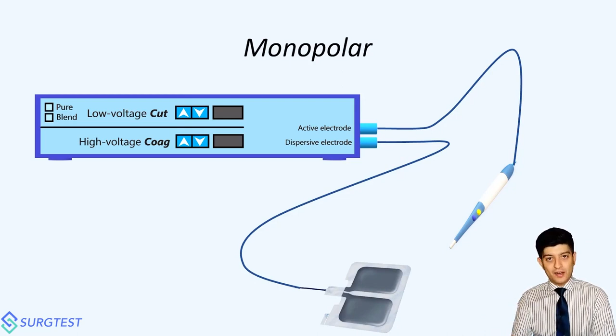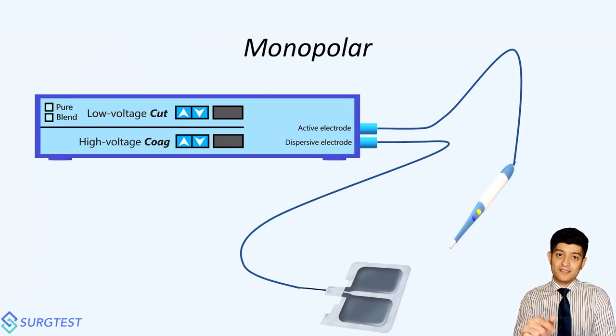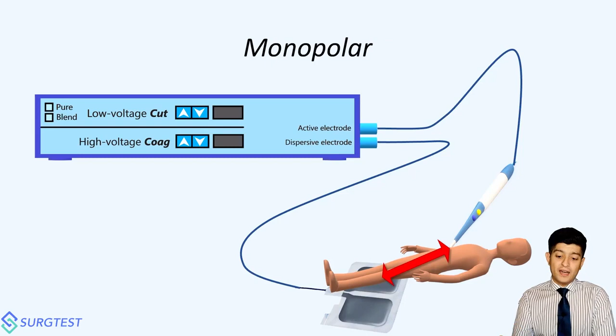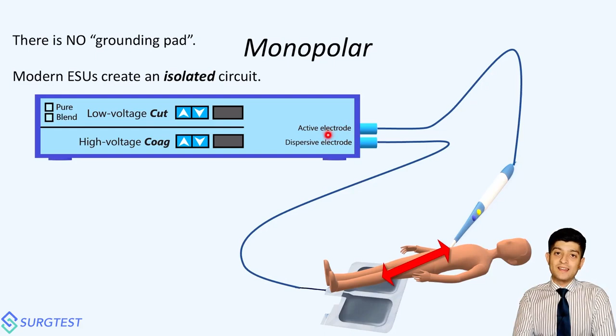So the amount of energy delivered to patient tissues was very inconsistent or unpredictable. As a result, we now have circuits where there is a dispersive electrode that connects directly into the electrosurgical unit. It does not get grounded, all right? That being said, the entire ESU by means of its power cord gets grounded, but not the patient. The patient is interposed between this cautery pen and the dispersive electrode, which is usually placed on the lower half of the body, and current flows between these two poles to finish off an isolated loop. So remember, there is no grounding pad. The circuit is entirely isolated, which consists of the ESU, the cautery pen, the patient, the dispersive electrode, with the current then finally getting completed at the ESU again.